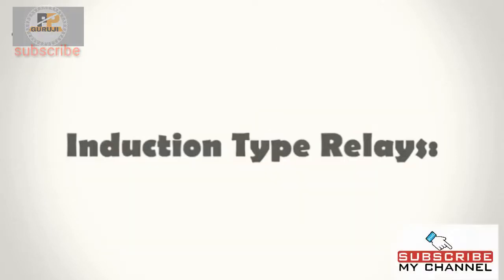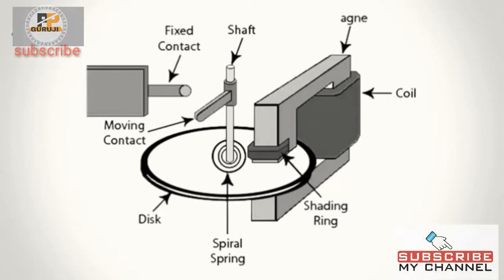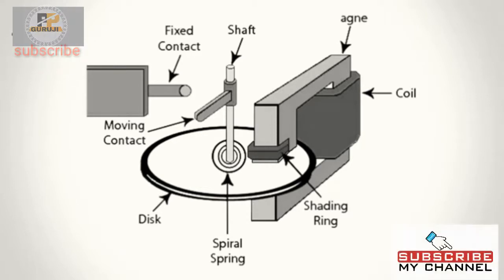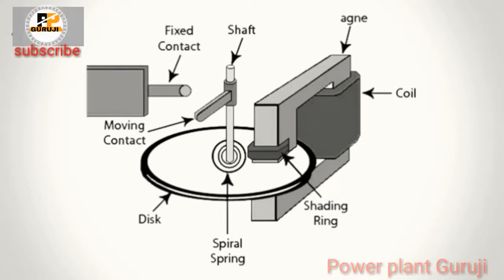Induction type relays. These are used as protective relays in AC systems alone and are not usable with DC systems. The actuating force for contact movement is developed by a moving conductor that may be a disc or a cup, through the interaction of electromagnetic fluxes due to fault currents. These are of several types like shaded pole, watt-hour and induction cup structures, and are mostly used as directional relays for power system protection and also for high speed switching operation applications.